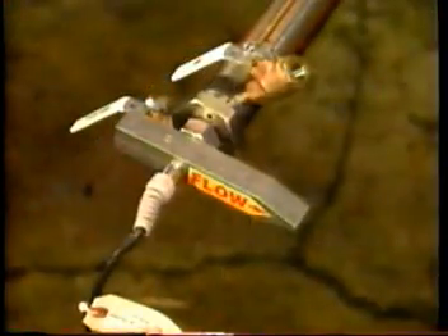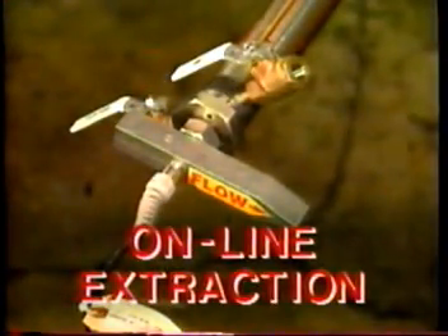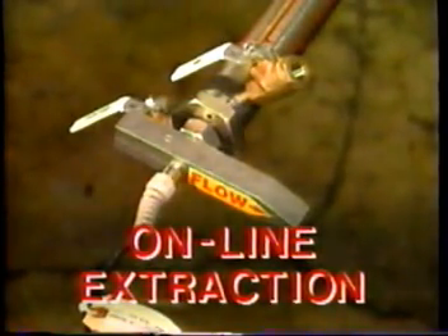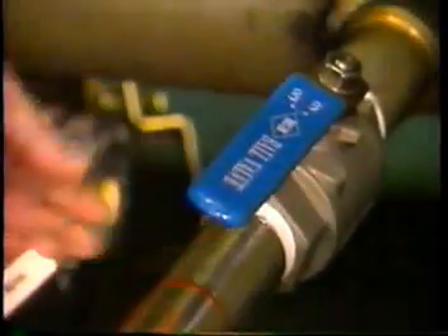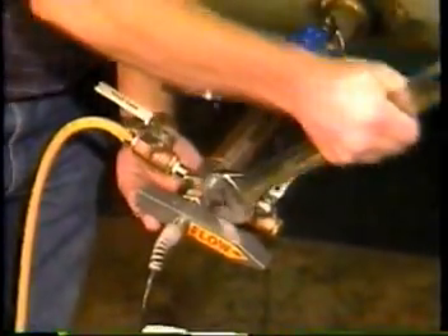During the life of the instrument, there will be times that you will want to remove the probe from the line. When the stock line is in operation, it's under pressure. The design of the extraction chamber, with its ball valve, pressure balancing water supply, and vent valve, permits removal and insertion to be performed safely in spite of the pressure in the stock line.